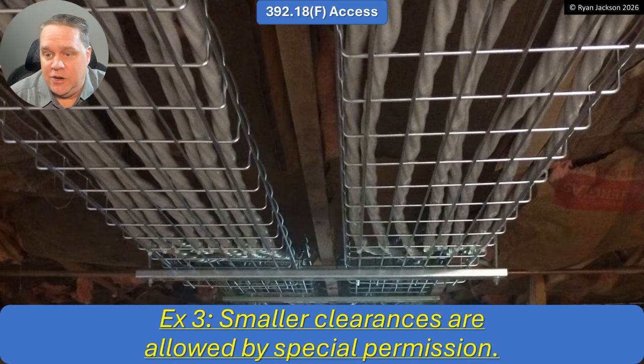But let's just be honest here. Who cares? You're not going to be splicing in that thing, right? This is not a supervised industrial location. I mean, this is an apartment building. You're not going to be splicing there. So why would it matter if I have less than 12 inches? As long as I have enough to, you know, maybe add another cable or remove one if I wanted to. So I would grant special permission on an installation like this to allow less than 12 inches.